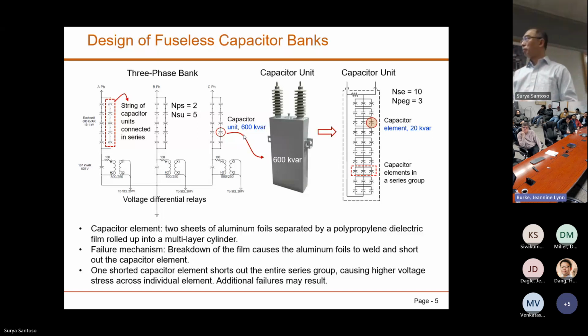Now, in a situation like this, if you only have several elements that are failing, that are shorted, and the differential voltage has not reached its threshold, the capacitor is just going to operate as usual. Nothing happens, it just operates. So that is the first possibility.